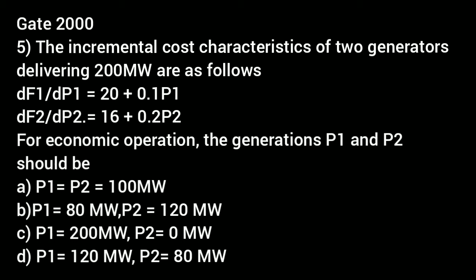Then the answer is: for economic operation, the incremental cost characteristics should be equal. That is dF1/dP1 is equal to dF2/dP2. That is 20 plus 0.1 P1 is equal to 16 plus 0.2 P2. By simplifying, we get the equation 4 is equal to 0.2 P2 minus 0.1 P1. And it is given that P1 plus P2 is equal to 200 megawatt. By solving equations 1 and 2, we obtain P1 is equal to 120 megawatt and P2 is equal to 80 megawatt. So let's move to the next question.